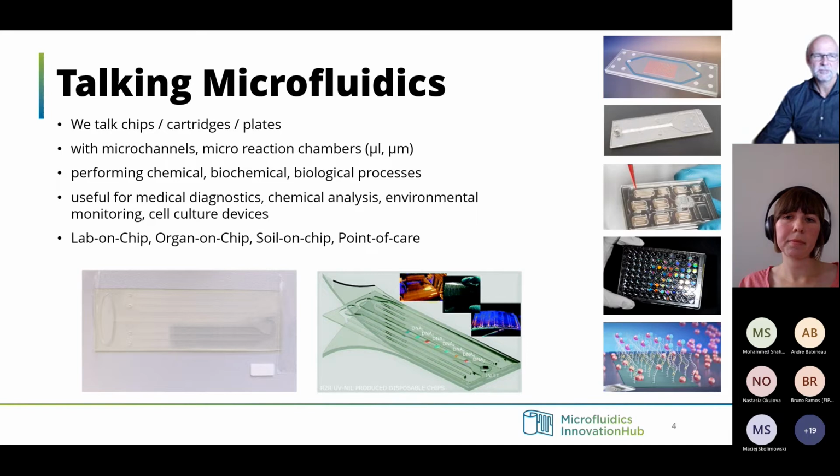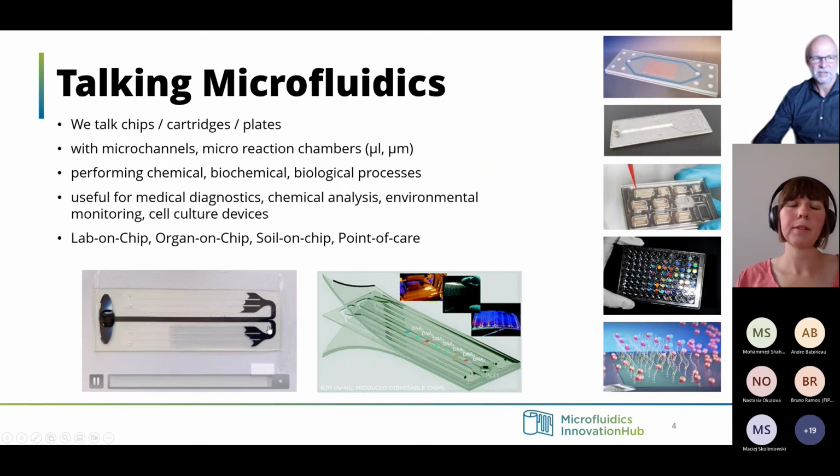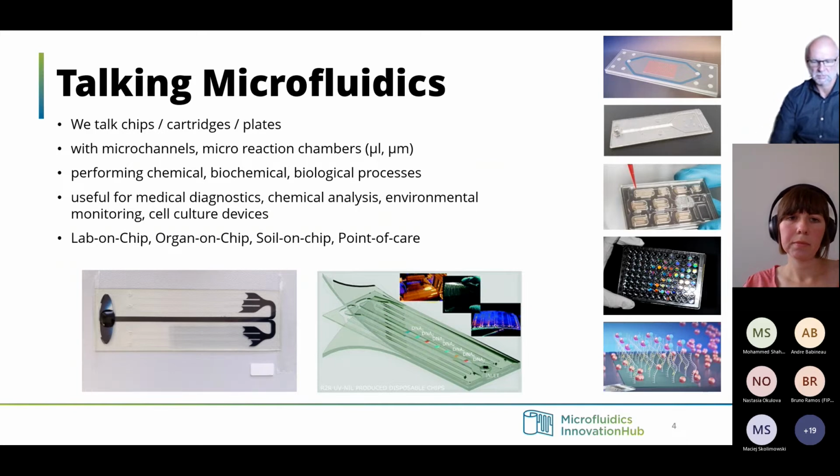That's actually the idea. To give you a hands-on idea or example how this actually works, we have here microfluidic chips. There's a drop of blood coming in, flowing along this channel driven by capillary forces. On the right-hand side, what you see, it hits various reagents. A chemical reaction is triggered. In these cases, it's a chemoluminescent reaction, and this chemoluminescent reaction is being measured by a readout device. And in this case, we are talking about antibody detection by using a microfluidic chip. Over here, you see the waste chambers, because all the blood or saliva or whatever liquid it is needs to go somewhere.